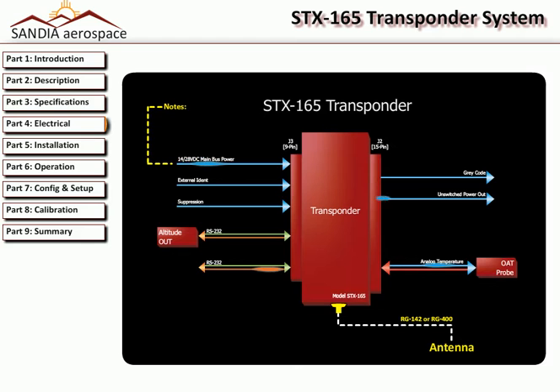Given the 21.2 watt maximum power consumption, it is recommended the power input be connected to a 1 amp circuit breaker on the avionics bus for 28 volt systems, and if installed in a 14 volt aircraft, a 2 amp circuit breaker should be used.